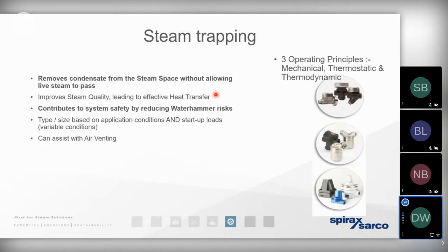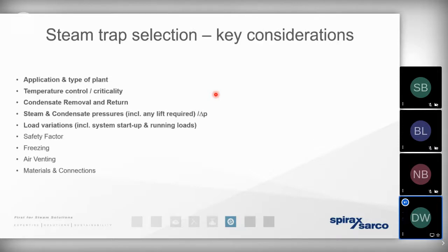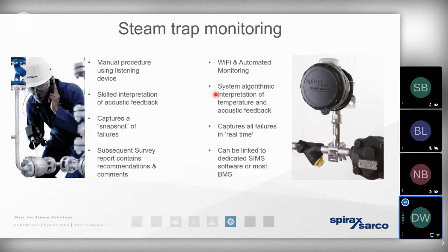But it's important that we not only select the correct type of steam trap and size the steam trap correctly, but also it's vitally important that that steam trap is monitored periodically to ensure that it's operating in the correct condition. We remember that steam traps can fail in the open position and steam traps can fail in the closed position. So when a steam trap's failed in the closed position, the condensate is likely to back up and flood the process. Heat exchange simply will not occur. But it can also mean that the condensate can back up across a steam trap and start to flood the distribution pipework, at which point we're at risk of that erosion, corrosion, and water hammer that we spoke about.